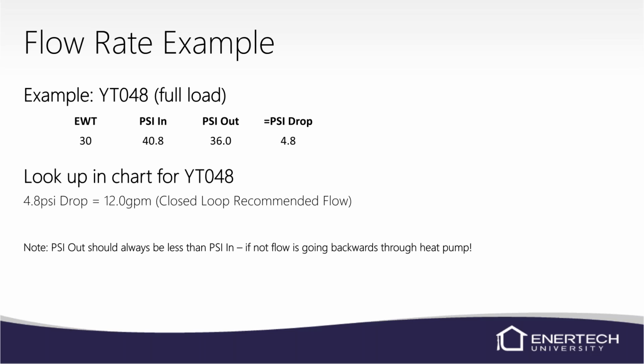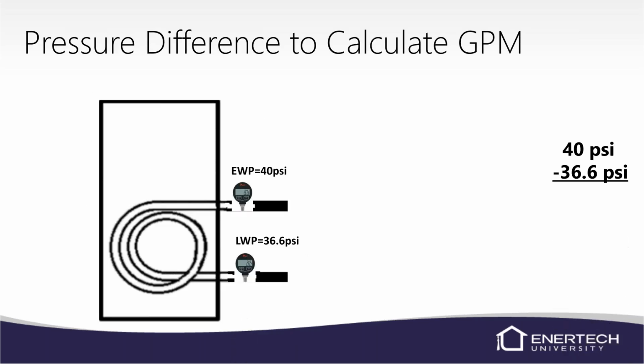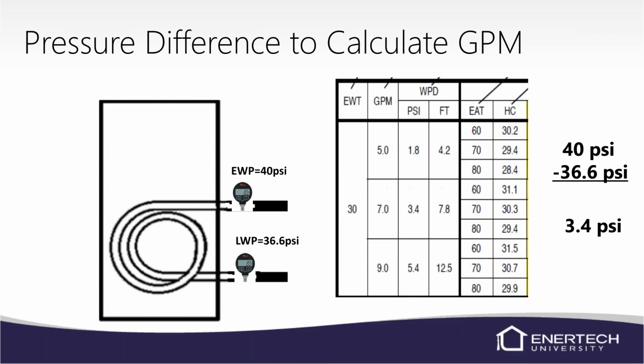Obviously, again, PSI out should always be less than PSI in. Obviously, pressure drop, there's your 40 and your 36, that would be your 3.4 pressure drop. Make sure that your pressure out, again, is lower than your pressure in. Then you'd look at your chart. You'd find your 30 degree entering water temperature, your 3.4 PSI pressure drop, and that tells us that our unit is moving 7 GPM at 30 degree, 3.4 pound pressure drop. That's why it's so important to have these manuals, because without them, you're not going to know what your GPM is on a pressurized system.